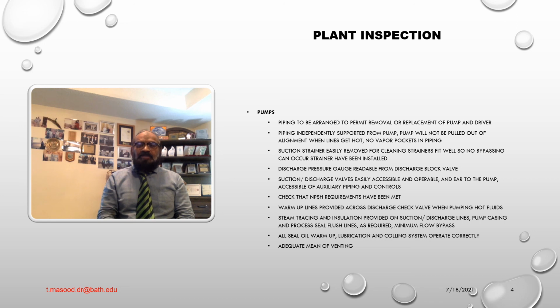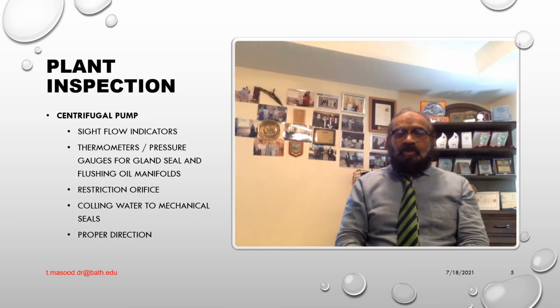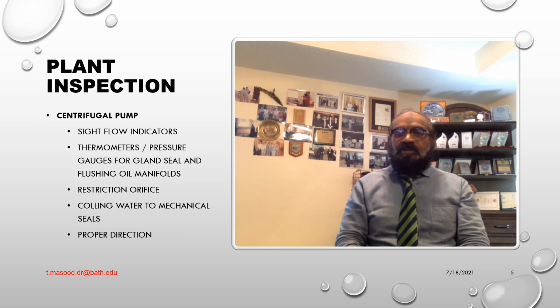Pump casing and process seal flush lines as required. Minimum flow bypass with suction surface if required. All seal oil warm-up extra lines have flanged connection and valves permits. So next is a centrifugal pump. Sight flow indicators if required. Inlet, outlet, shut-off valves on cooling water lines. Thermometers, pressure gauges for gland seals and flushing oil manifolds. Restriction orifices if required present in seal flush manifold piping. Pedestals on pumps operating over 500 degrees F or 260 degrees C should be water cooled.